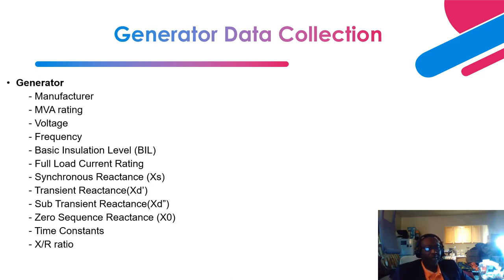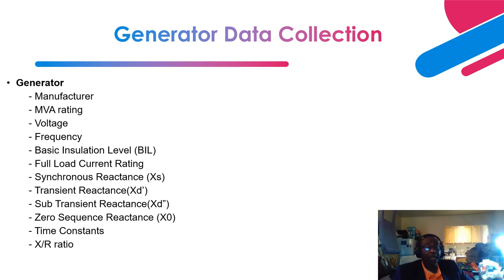For the generator, you need the manufacturer, MVA rating, voltage, frequency, basic insulation level, and full load current rating. For the reactances, you need the synchronous, transient, and sub-transient reactances, plus the zero-sequence reactance. You also need the time constants — synchronous, transient, and sub-transient — which you'll also need for transient stability studies. It is best to collect all this data when you are in the field. You also need the X/R ratio.